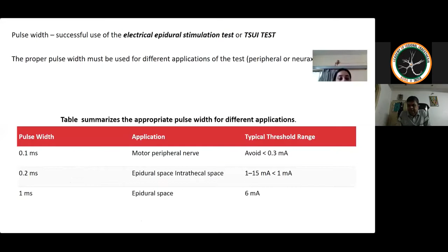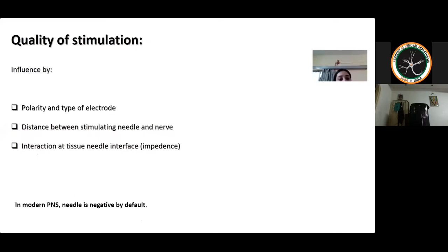Now, the quality of the stimulation is mainly defined by the polarity and the type of the electrode, the distance between the needle and the nerve, and the impedance, that is, the interaction at the tissue-needle interface. Electrical polarity is defined as the directional flow of electrons from the negative pole towards the positive pole. Here, in the circuit, the negative pole, that is the cathode, is connected to the stimulating electrode of the needle, which is black in color, and the anode is connected to the skin, which is red in color.